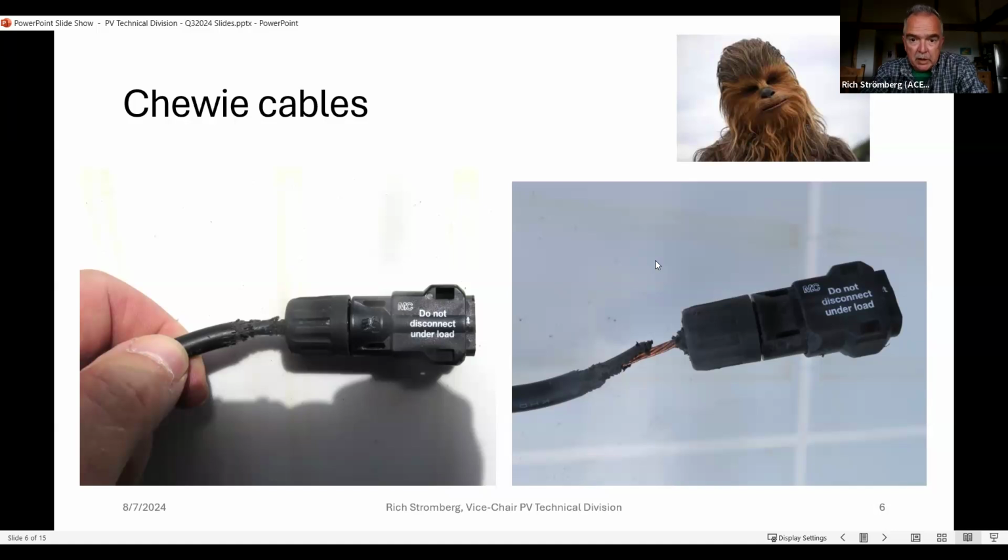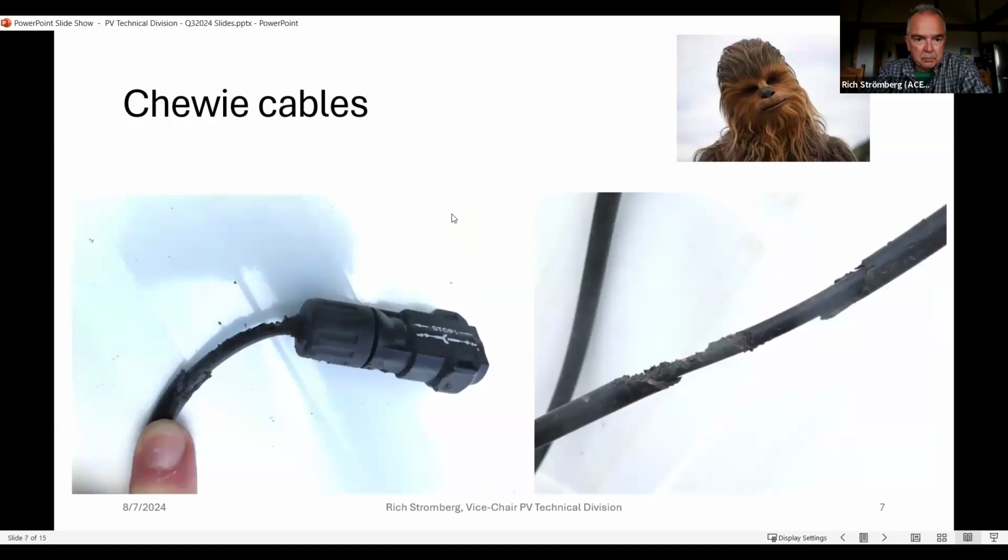So there were these. And now for this, what we would do if this was the only damage on this particular cable, we'd cut it here and then we'd put on a new connector. And same with this. If you had an electrician or someone suggesting to just wrap electrical tape around this, no, that does not suffice as reliable protection against shock hazard once the damage has occurred. You really need to cut the cable and then put on a new connector.